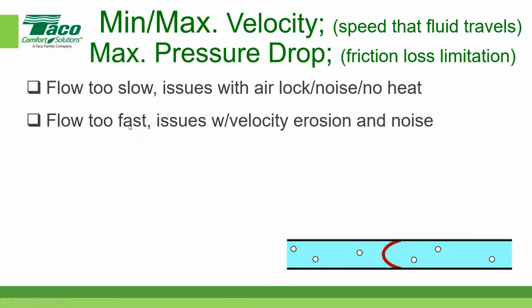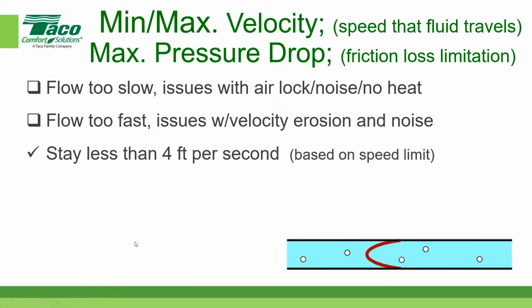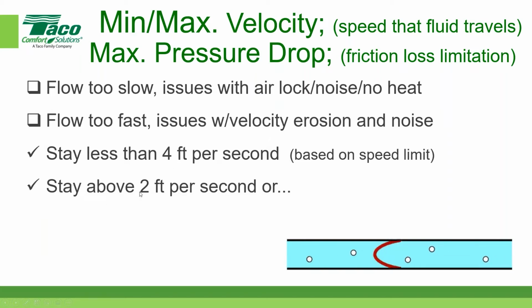Too fast is a little more intuitive. It just says I could potentially run the fluid so fast that I could eat the pipes up. And I can hear the rushing sound of the water inside the pipe, and that's never a good thing. If we had more time, I'd do some more examples, but generally speaking, you should never be able to hear the fluid running through the pipe in a closed loop heating or cooling application. That means if you can, your velocities are probably way too high. And that's what these next few slides will build on. Kind of the rules here is stay less than 4 feet per second and stay above 2 feet per second.